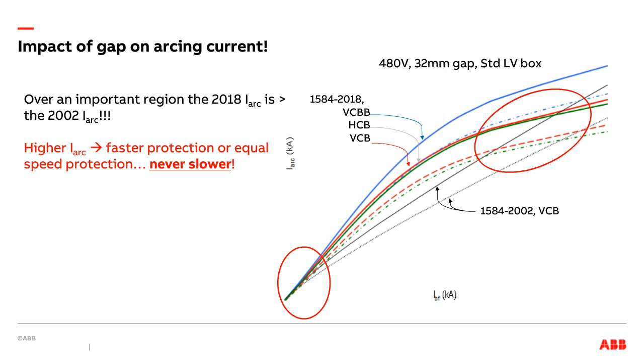But when you look at the range of IBF, you'll see that that tends to be for very high bolted fault currents, 85 kA, 75 kA, 90 kA, 100 kA, values that we don't typically run into in real-world systems. Most real-world systems tend to be 55 kA and below. 50 to 20 kA, 50 to 15 kA, you're dealing with panel boards, motor control centers, switchboard, switchgear, and your typical industrial commercial facilities. If you're downtown New York City, completely different kind of worms, because there you have 200 kA systems. To tell you the truth, you shouldn't be doing energized work in those situations, period, end of discussion.